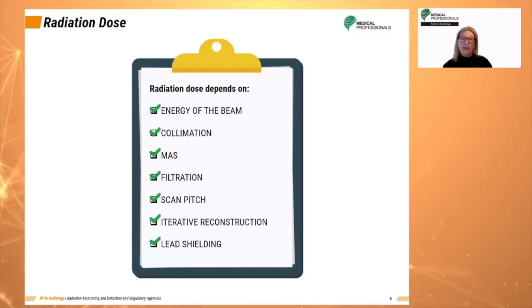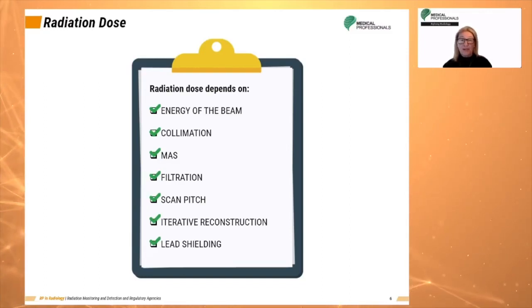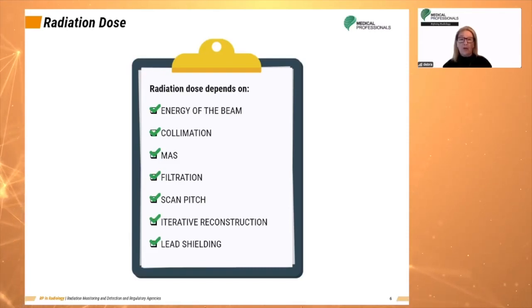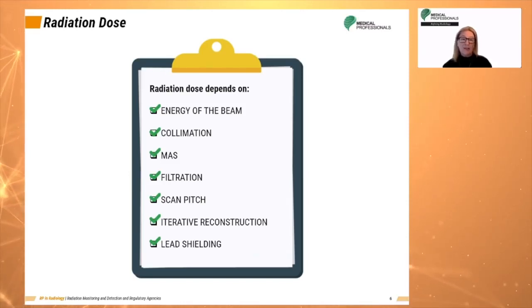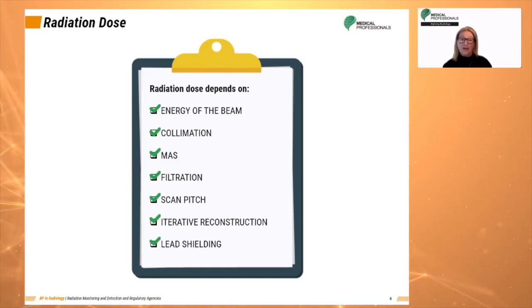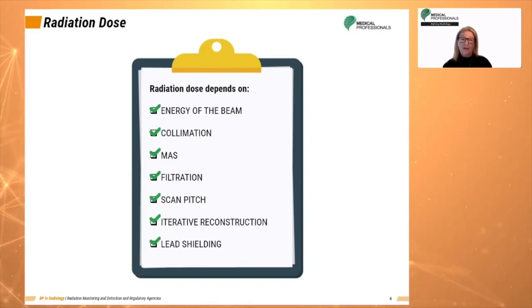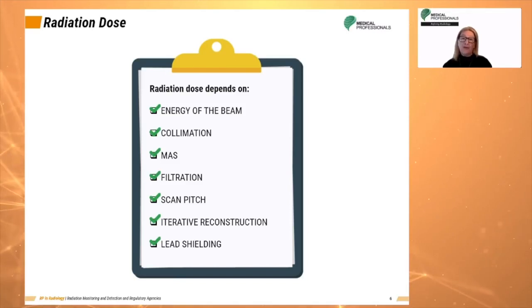Iterative reconstruction can be used to reduce dose levels while maintaining acceptable noise levels. It refers to iterative algorithms used to reconstruct 2D and 3D images. In computed tomography, an image must be reconstructed from projections of an object. Generally, shielding is not utilized in CT because the beam is so tightly collimated to the slice thickness.